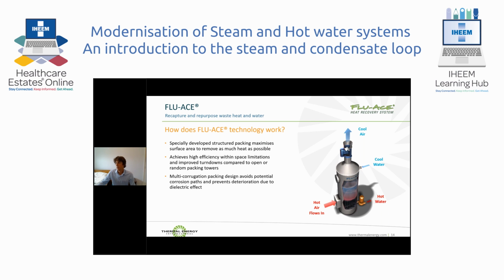So this is a FLU-ACE. How does it work? We take the hot air from the boiler, the CHP, whatever the source is, and we draw it up through our heat recovery system. We have a fan which draws the hot air from the existing exhaust stack. This means we're never going to put a back pressure onto your boiler or CHP plant because we're actually sucking the air into our system.